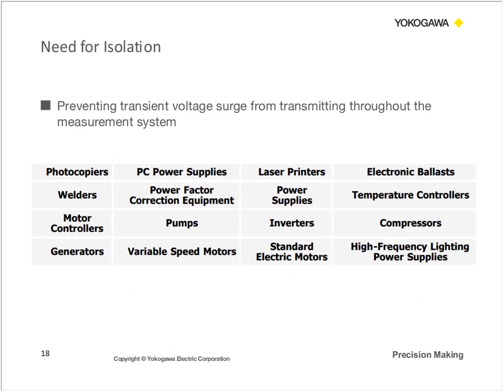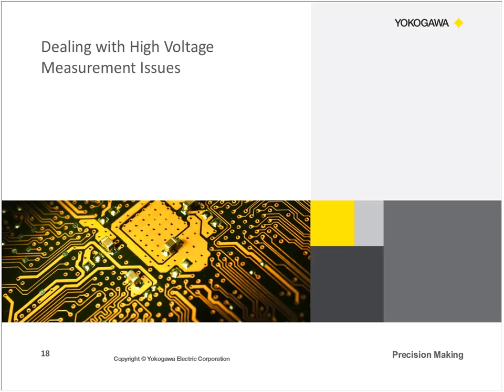Okay, one of the last cases, obviously, is preventing transient voltages from surging throughout your measurement system. So transients affect a large amount of equipment, and this can include, as I've listed out here, pumps, inverters, motor controllers, various variable speed drives, compressors. So if you're working with any of these pieces of equipment, please be sure to think about using isolated data acquisition as well as external isolation to prevent these transient voltages from surging throughout your system and damaging everything.